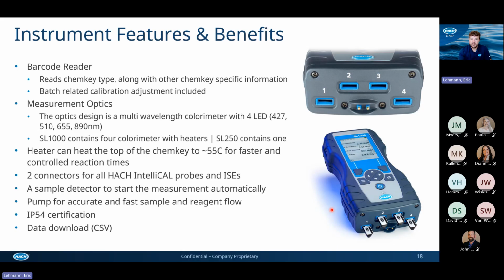The sample detector, that's going to be these 2 contacts right here. Once we put the sample into our sample cup, it's basically a conductivity sensor, creates a conductance that's going to tell the instrument that it's in contact with the sample, and it can start drawing sample up into the chem keys. It uses pumps to draw that in. IP54 certification, so it can tolerate some moisture. Obviously, you don't want to drop this into a bucket, but it can tolerate some moisture getting wet.